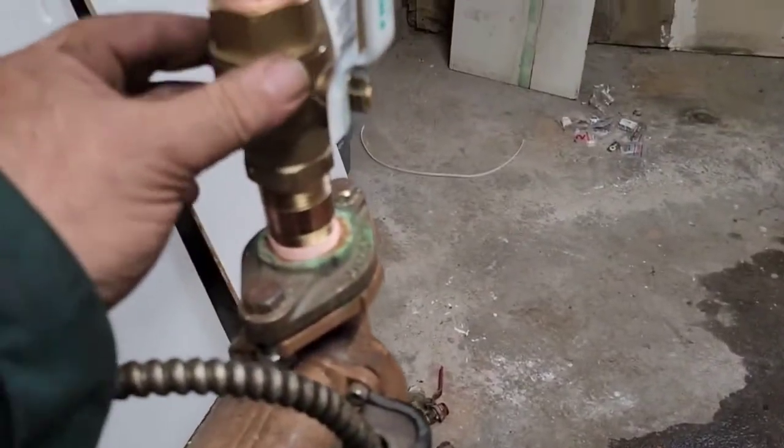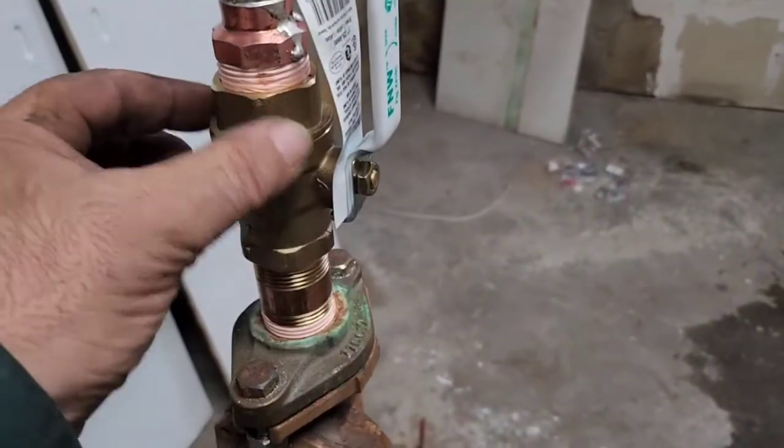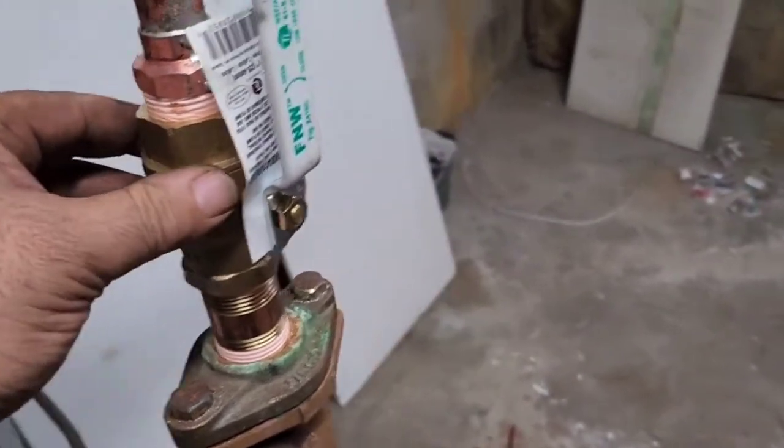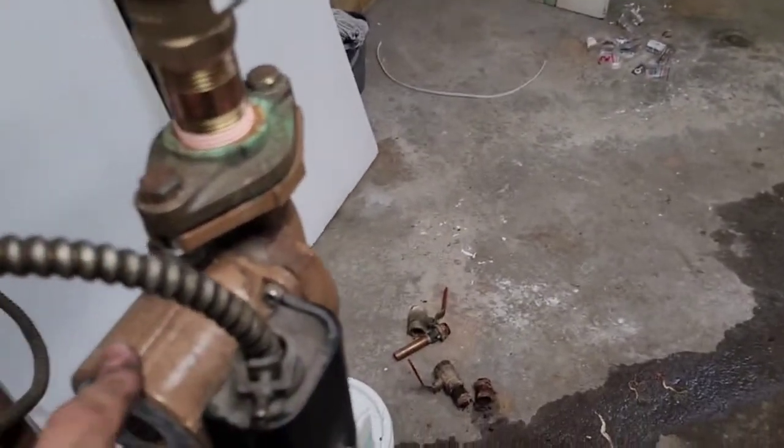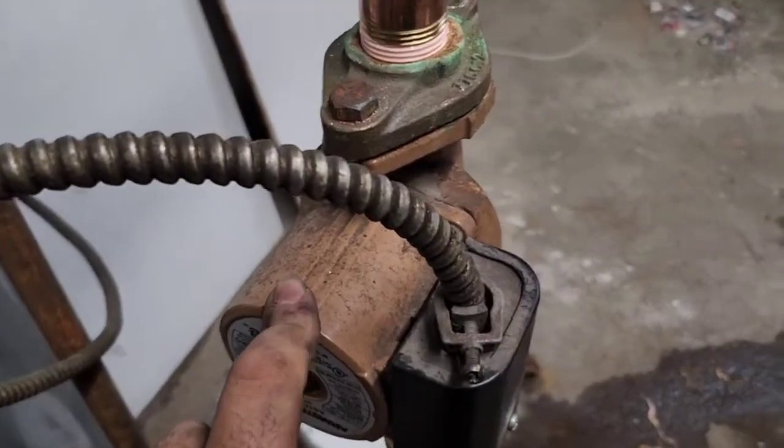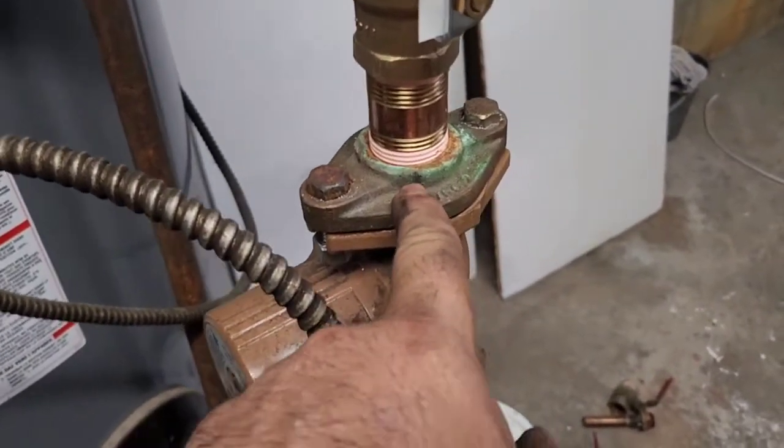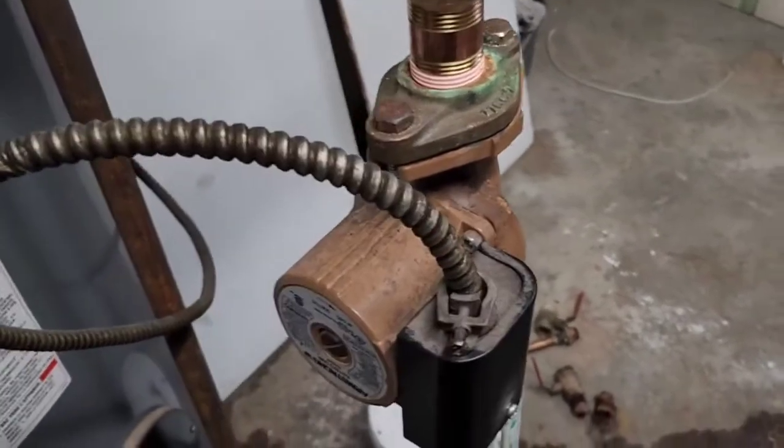It will say G and W, that means it could be used for natural gas and also water. Your pump has to be rated for domestic hot water. Your flanges have to be bronze flanges. You can't use cast iron flanges for domestic hot water.